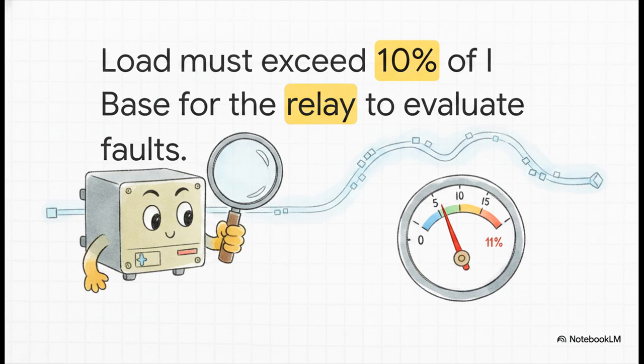Before the relay even bothers trying to figure out if a wire is broken, it checks the overall system load. It essentially requires the baseline current to be greater than 10% of the base current rating. If there just isn't enough power flowing through the system to begin with, the relay simply won't engage this specific diagnostic logic. It needs a solid, healthy baseline to even start looking for anomalies.